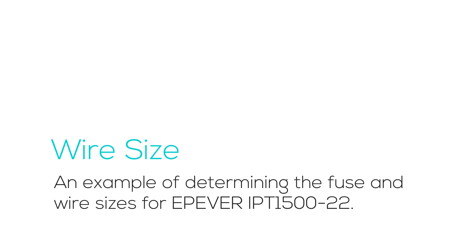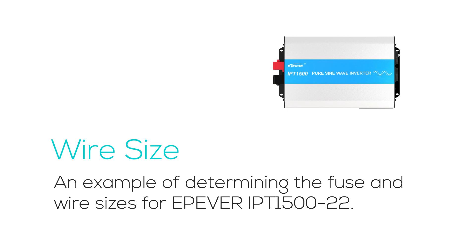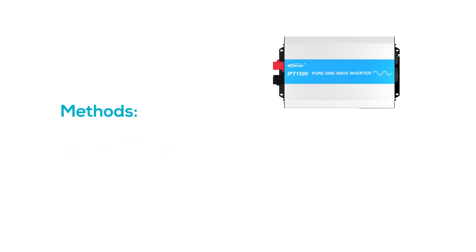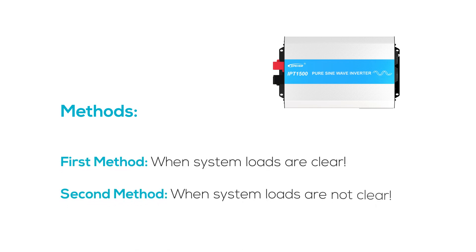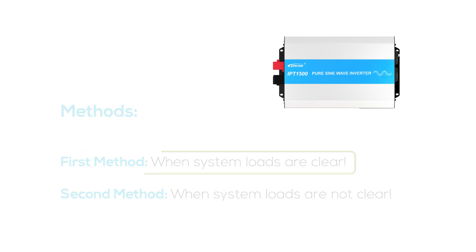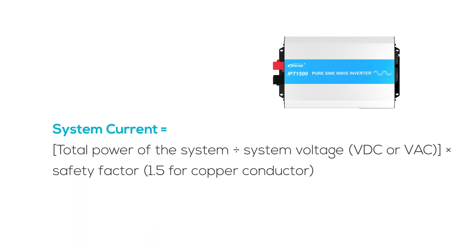In this segment we determine the wire and fuse sizes for a system with the IPT 1522. Two methods are proposed depending on whether load details are known. First method — when load details are known — there's a formula for system current calculation: sum the power ratings of all devices running simultaneously and divide by the system voltage.